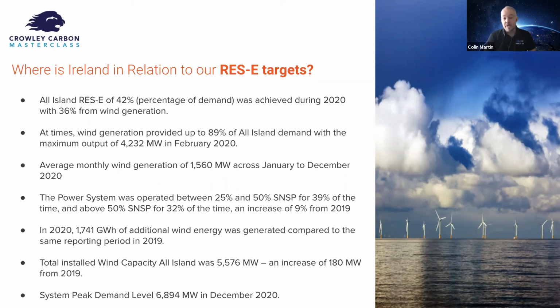Now, at times in Ireland, it can be even higher than that 40%. The instantaneous peak reached was 89%, back in February 2020. Generally the grid operators are not too happy with that level at the moment, but they are working to have a higher level of sustained instantaneous demand being generated by these non-synchronous sources. So what exactly does that mean? Basically, they're looking to move up towards 80, 85% for longer, from wind and other renewable generation sources.